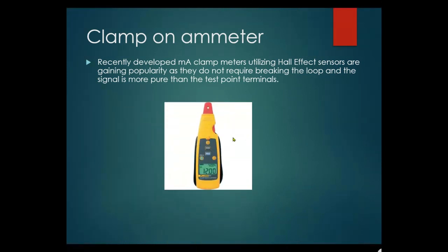The milliamp clamp meter, like the Fluke version, has a very small aperture — similar to a clamp-on ammeter for larger currents but scaled for milliamp-level signals. They're fairly accurate and you can put them anywhere on the loop because the loop is a series circuit — the current is the same everywhere in the loop.